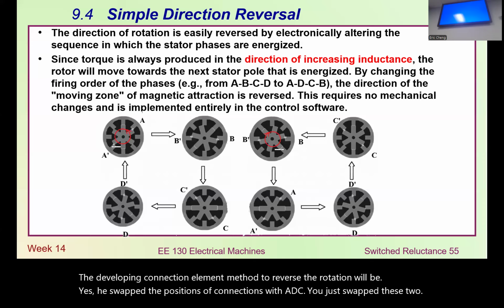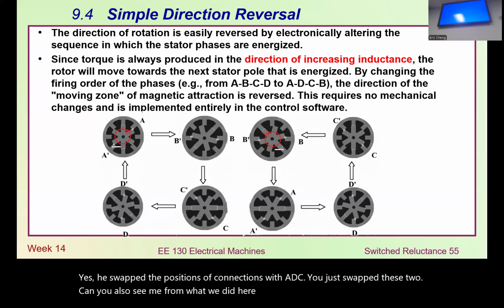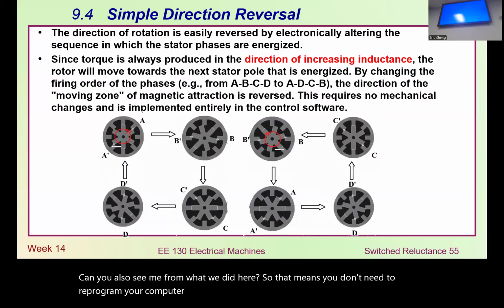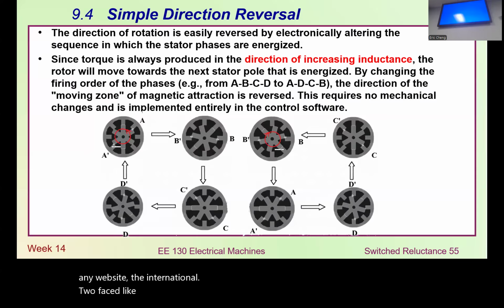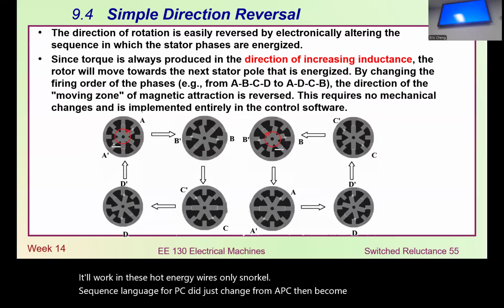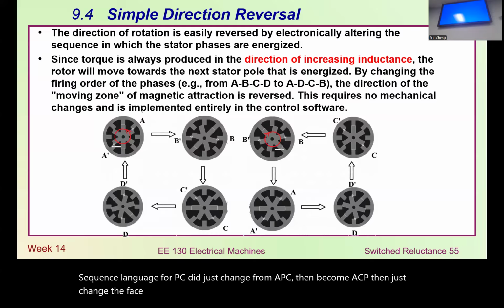Similar to what we did here, that means you don't need to reprogram your computer, you just swap two wires. In the future, if you go to any industrial motor rotating instrument, you just swap two phases like this to change the rotation. You can swap any two wires, and that automatically changes the phase sequence. When you swap B and C, you change from ABC to ACB, changing the phase sequence.